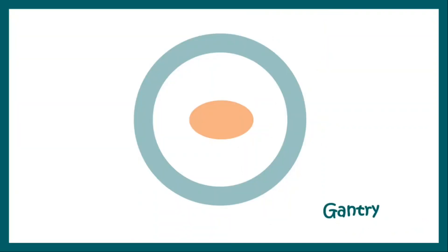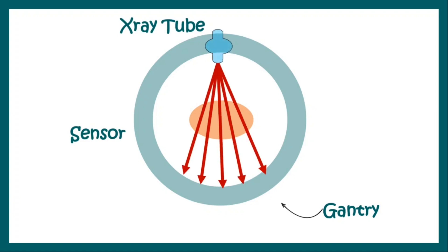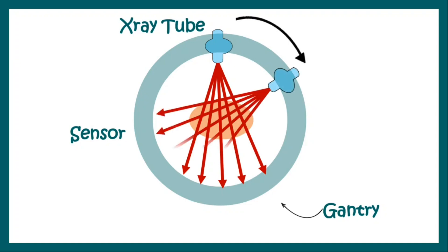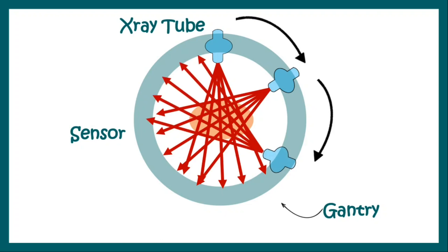The gantry has sensors all over its body and has X-ray tubes. These X-ray tubes fire X-rays towards the body and the sensors pick up and form an image. The X-ray tube then rotates and gives another projection, then rotates again and gives another projection. This is how multiple projections of the same slice of the body are taken. These multiple projections are processed using computer software and finally overlapped to generate one single high-resolution image.